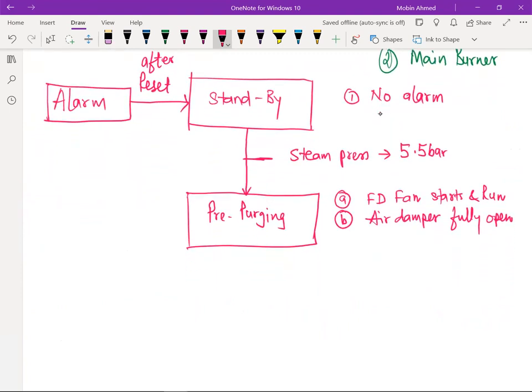So in the pre-purging, the air damper is fully open, and then there is your FO pump. Generally, it is going to start and run. Once it is on, it is always running, and sometimes it starts and runs. In some systems, as soon as it comes from the standby, first the FO pump will start. In some systems the pump runs continuously, but it circulates. It is not stopping. So the FO pump starts and runs at this point.